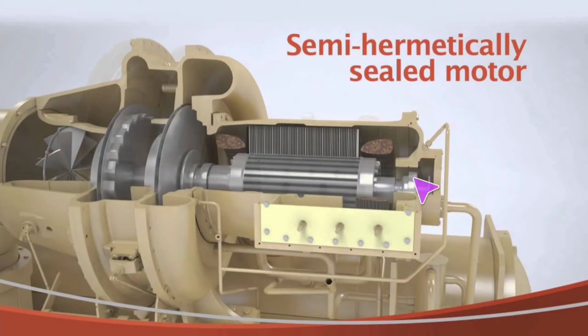End of the day, you've got a ball bearing back here, you've got your bearing assembly up here. This front assembly does have a journal bearing, so just be aware of that, and I'll explain that deeper shortly. This is a very accurate representation of the guide vane assembly for the first stage, and these are the armatures that you see. If you go look at my other video, you'll see these exact same armatures that control them. And these little ridges here are part of that vane assembly and its ability to control. These motors are semi-hermetically sealed, just like the depiction says. This is all part of the refrigerant stream. It's all built in, so some of the others, say York, for example, some of their centrifugal chillers, the motor's external. It's not part of the refrigerant stream.